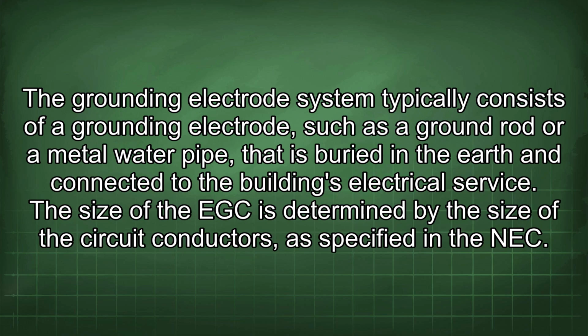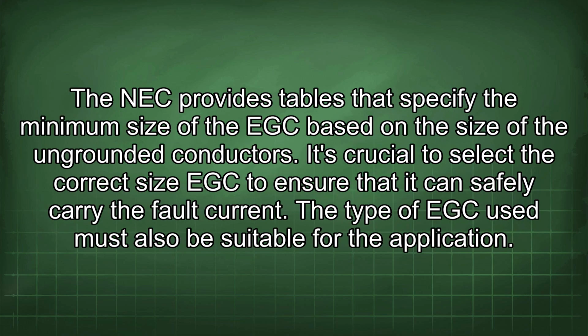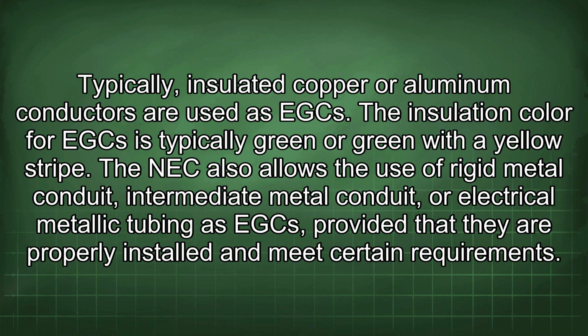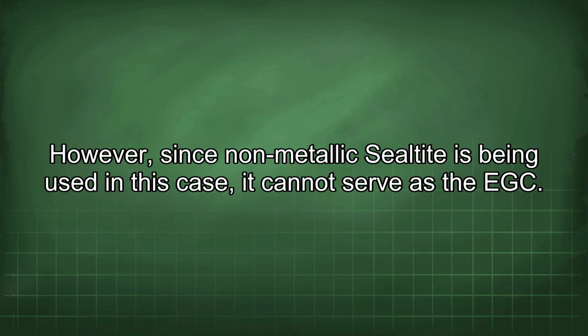The size of the EGC is determined by the size of the circuit conductors, as specified in the NEC. The NEC provides tables that specify the minimum size of the EGC based on the size of the ungrounded conductors. It's crucial to select the correct size EGC to ensure that it can safely carry the fault current. The type of EGC used must also be suitable for the application. Typically, insulated copper or aluminum conductors are used as EGC. The insulation color for EGC is typically green or green with a yellow stripe. The NEC also allows the use of rigid metal conduit, intermediate metal conduit, or electrical metallic tubing as EGC, provided that they are properly installed and meet certain requirements. However, since non-metallic Sealtite is being used in this case, it cannot serve as the EGC.